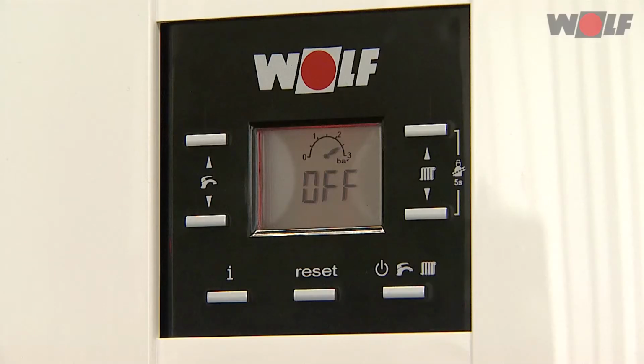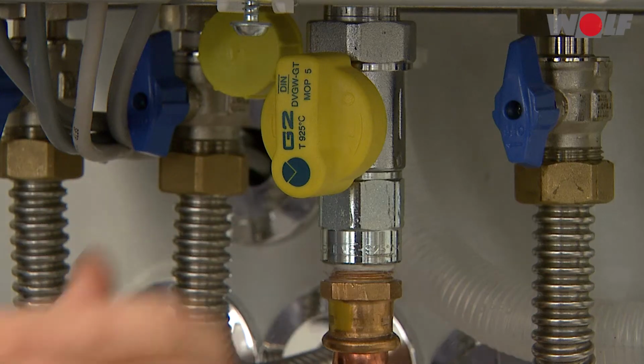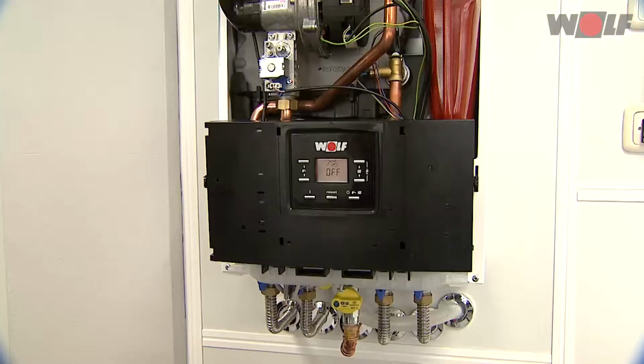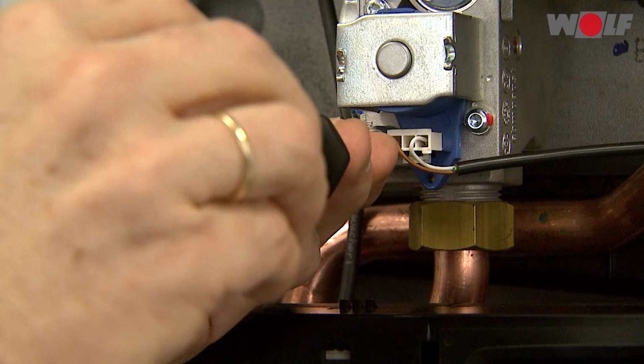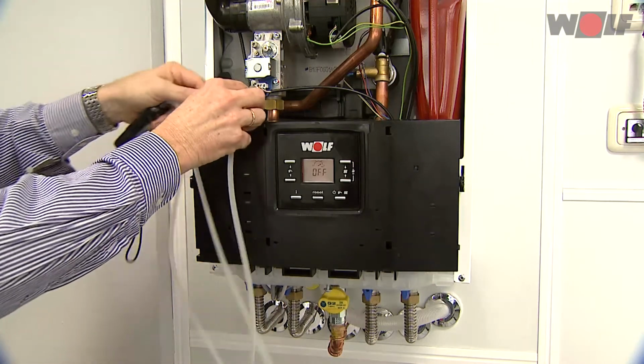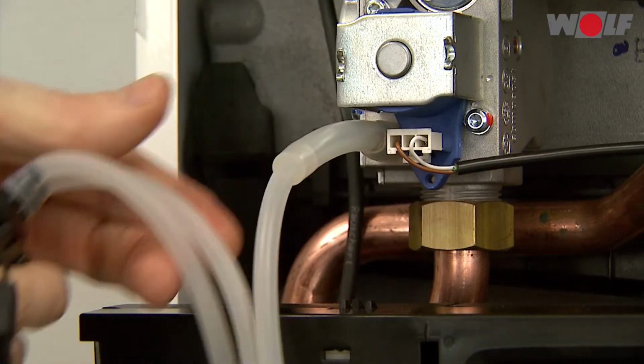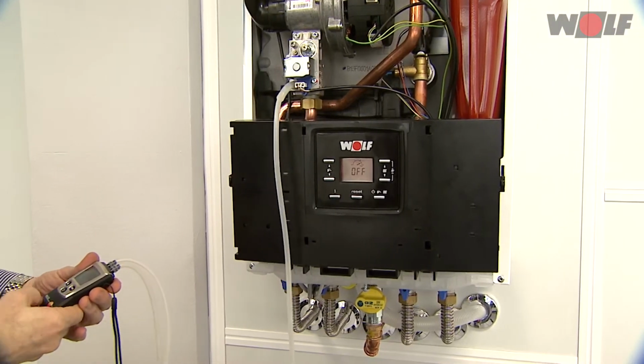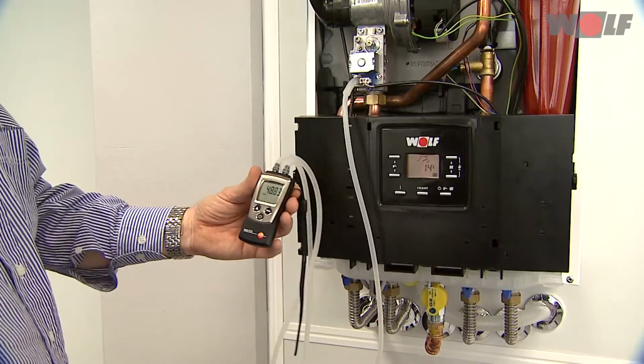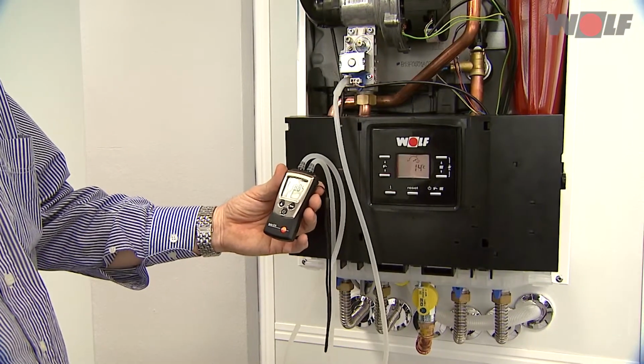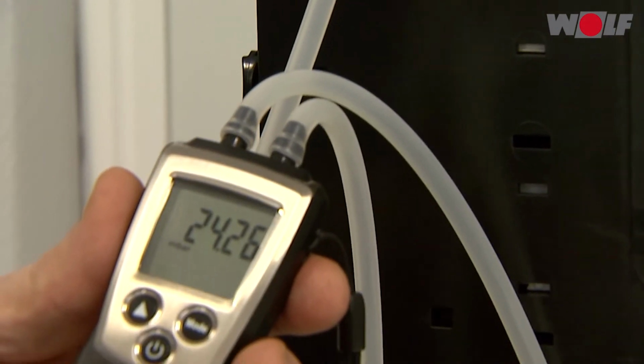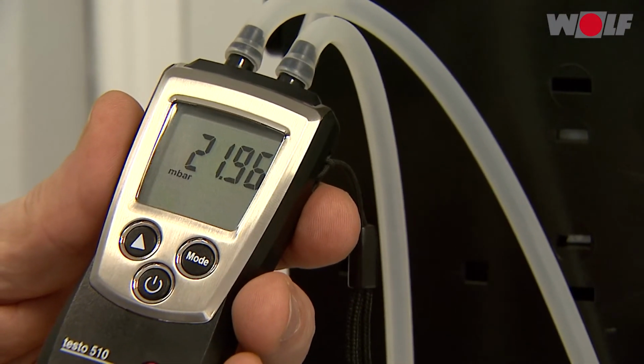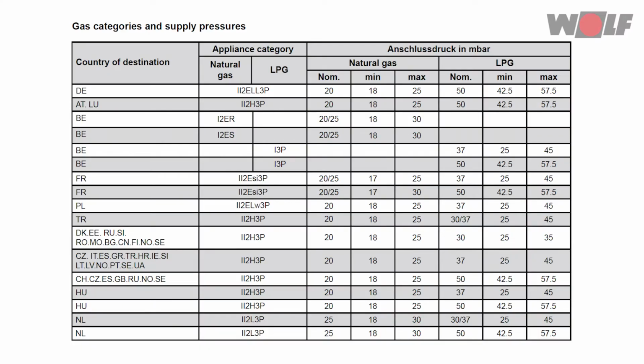Checking the gas supply pressure. The gas boiler must be switched off. Close the gas ball valve. Loosen screw C on the gas test connector of the gas combination valve with a screwdriver. Do not remove the screw. Connect the pressure gauge. Open the gas ball valve. Switch the gas condensing boiler on by pressing button 5. After the boiler has started, read the supply pressure on the pressure gauge and enter it into the commissioning report.